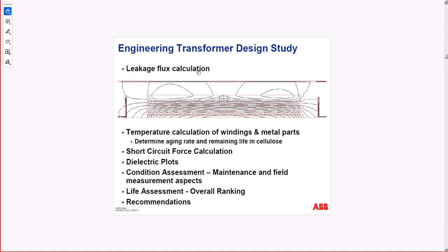Leakage flux. Well, this happened also in Pickering, transformer unit 5, main output transformer. We got the magnetic core inside the main tank, right? The magnetic core should have a certain definite position, but if it's moving during transportation, or moving during a severe short circuit because of the forces, definitely this will get the magnetic core of the transformer closer to the tank, or by design, by miscalculation, so the design wasn't proper and you got field, as you can see at the top, closing to the tank top cap.